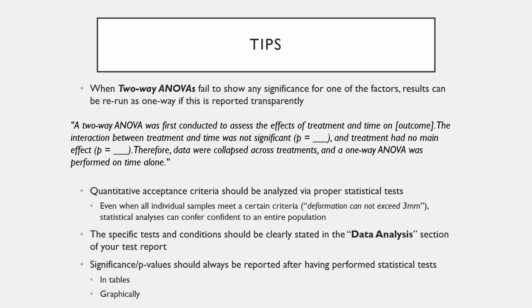So that's absolutely permissible. Going back to the acceptance criteria in your reports, you always want to analyze your quantitative acceptance criteria, meaning ones that have to do with either differences between batches, differences from one another, or to a certain specification that you have, with the proper statistical test.